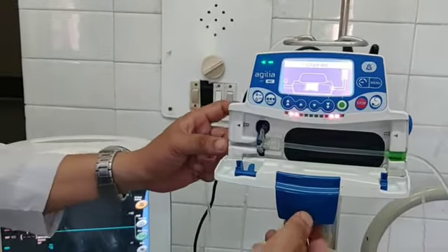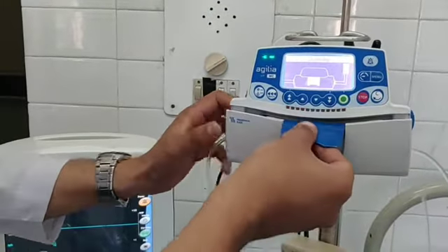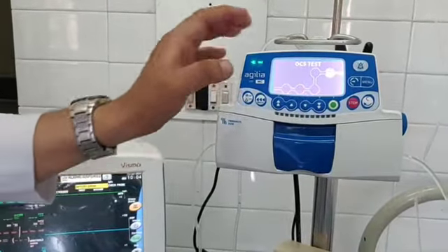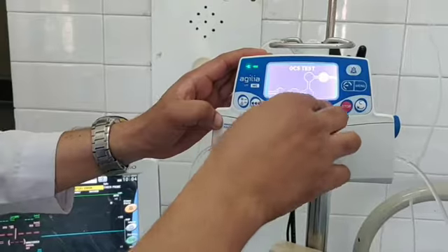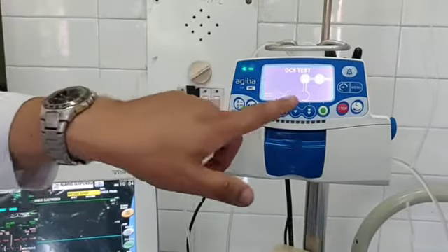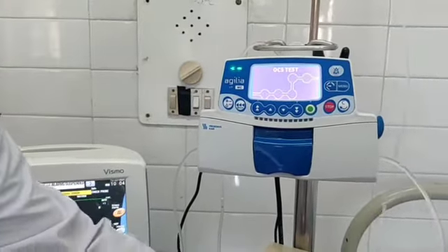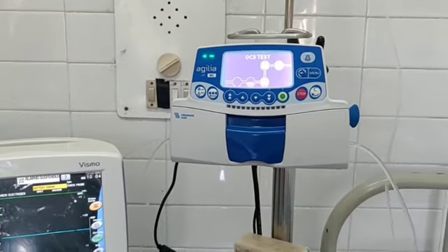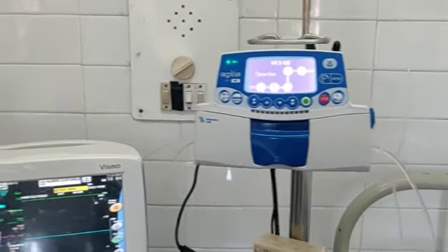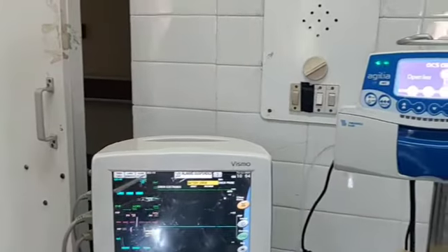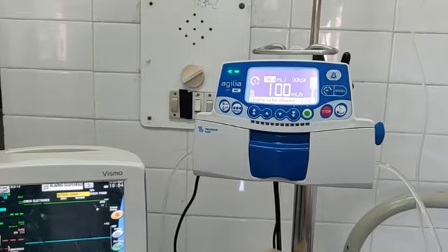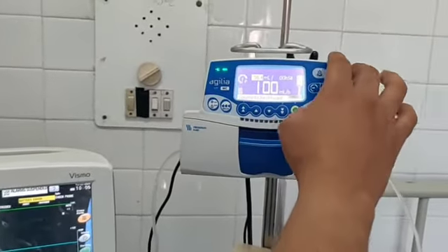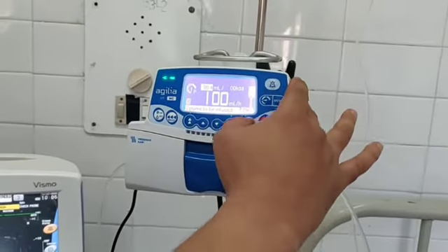and it is taken out. And once it is done, the infusion pump door is closed, and then it has to be checked for the pressure line. So we can start checking the pressure. Here it demonstrates the pressure check, and we must make sure that all the lines are open during this pressure check. So now it shows that the pressure is okay. Now from here we should start setting the infusion settings.